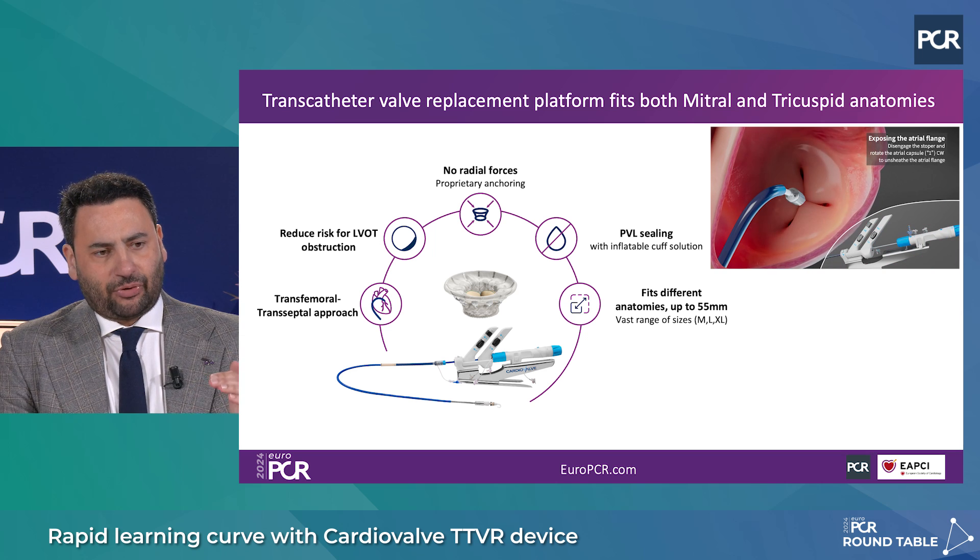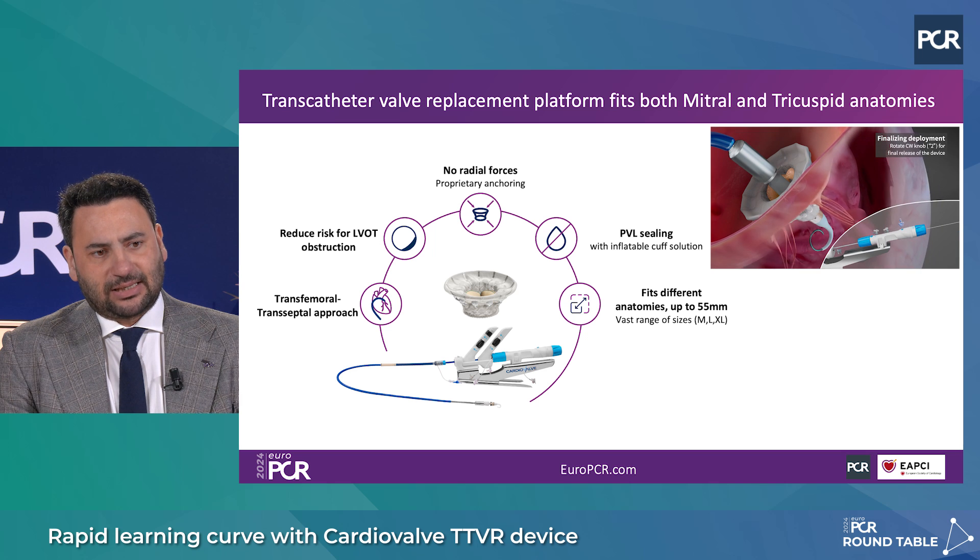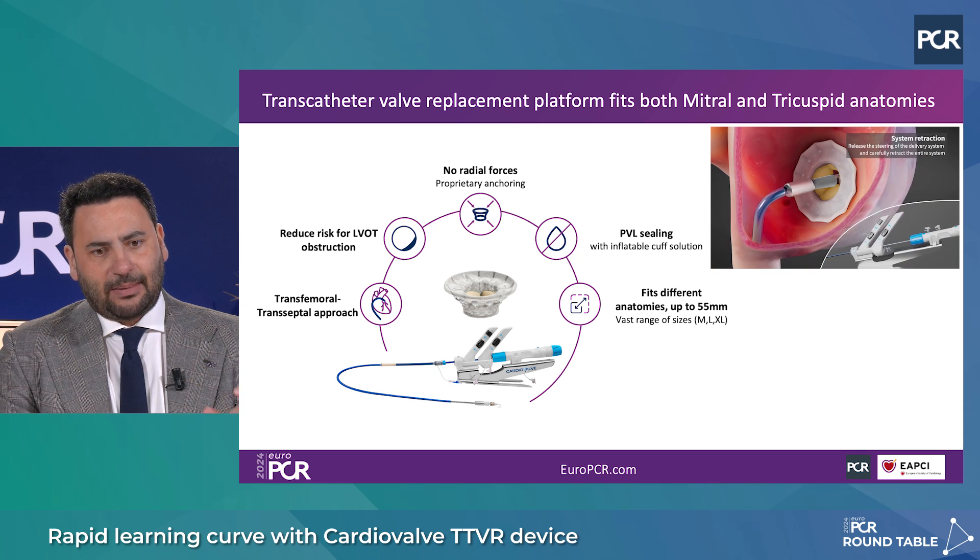It comes in three different sizes and importantly also has a proprietary anti-PVL system — an inflatable cuff that uses blood entering during systole to create a cuff that prevents paravalvular leakage. This is very important because in the tricuspid space we are usually dealing with large annuli, so it's good news to have this.